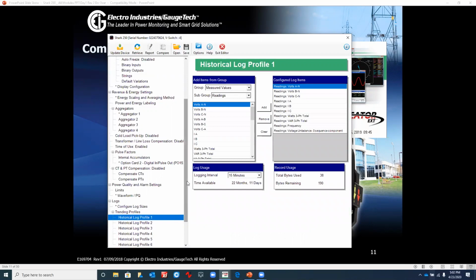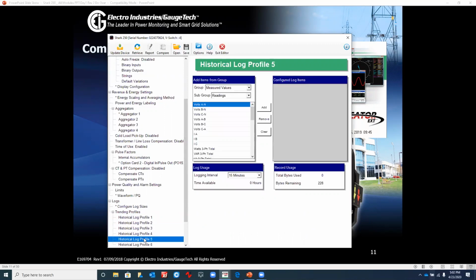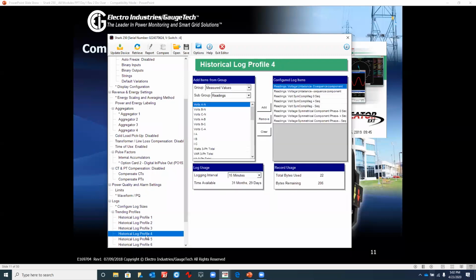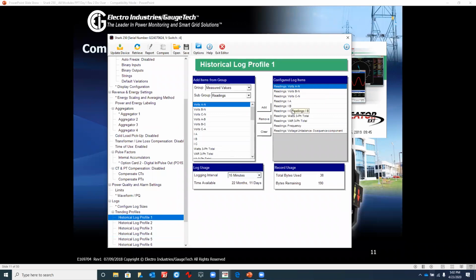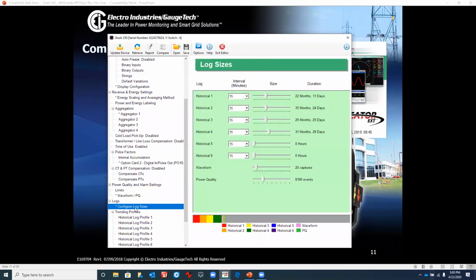So let's talk about the historical logs. I'll go through real quick historical log 1, 2, 3, 4. The meter is pre-programmed with 1, 2, 3, 4 logs that are set up to retrieve data. Historical log 1 has volts A to neutral, B to neutral, C to neutral, I A, B, C, watts total, vars, frequency, and voltage. All that information is going to be stored in the meter. It will be stored in 15-minute blocks, and you get almost 22 months of data, almost 2 weeks, so it's a lot of data you can store for log 1. This is determined by the slider that we talked about before.